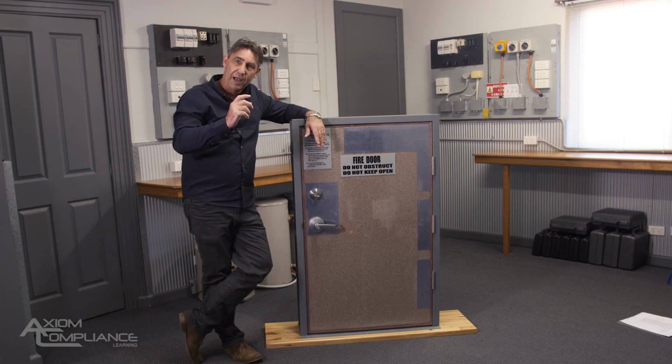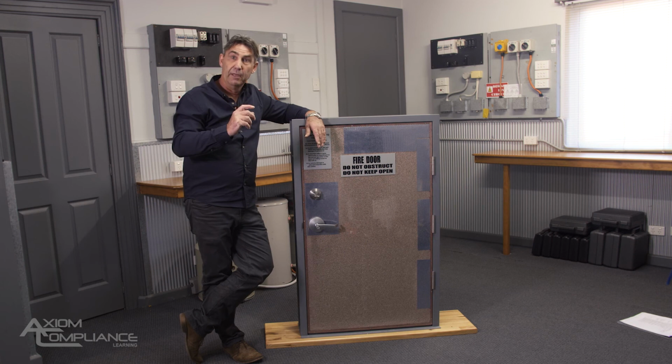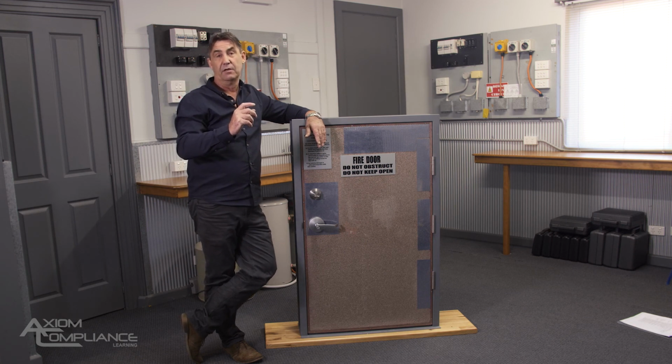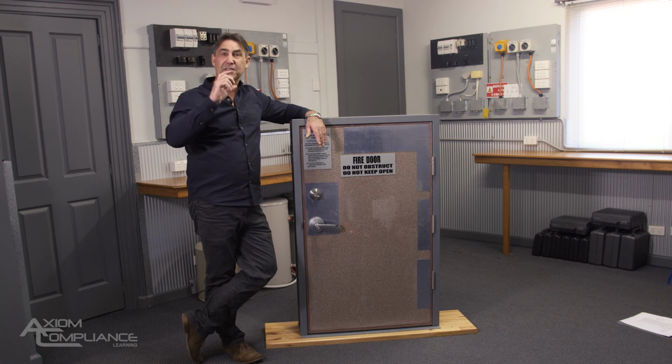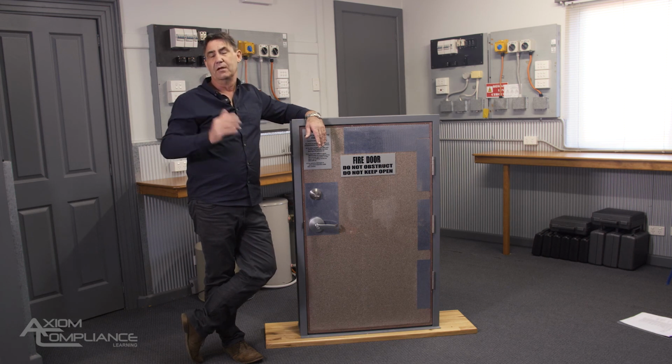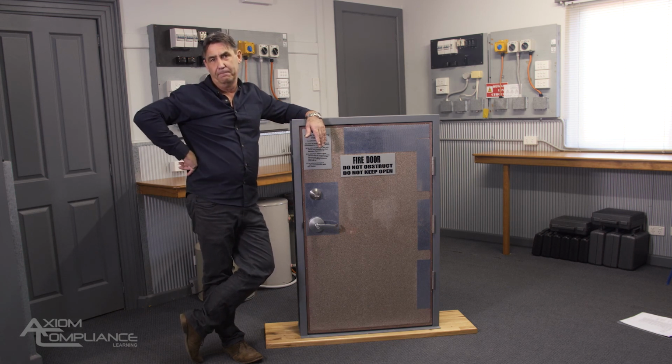If the door is a 2-hour fire rated door, all the hardware must be 2-hour fire rated. So you can get a 1-hour fire rated door or a 2-hour fire rated door, and that's indicated on the label. And in your course notes, it clearly tells you what those numbers mean on that label for fire rating.